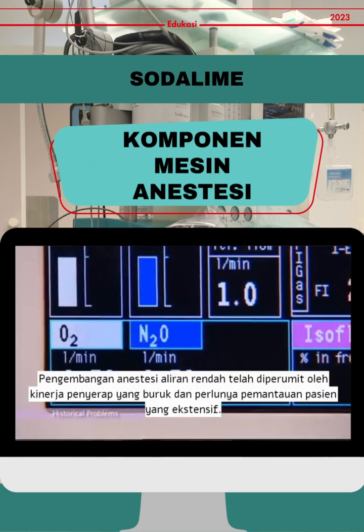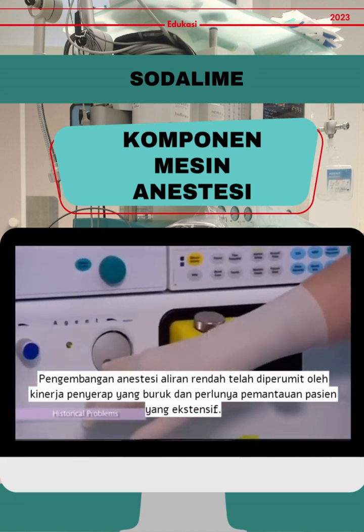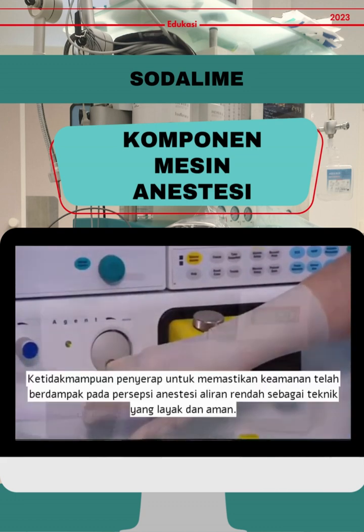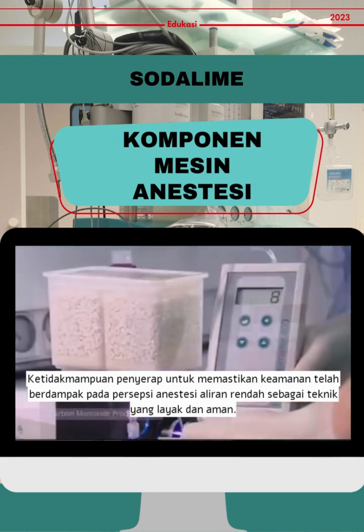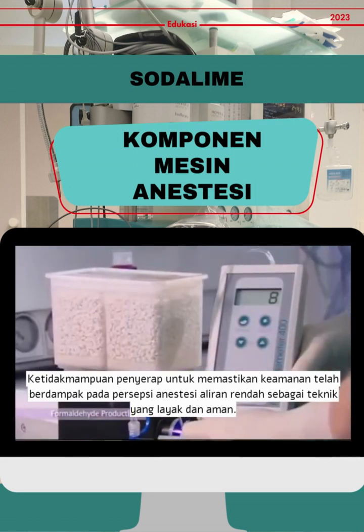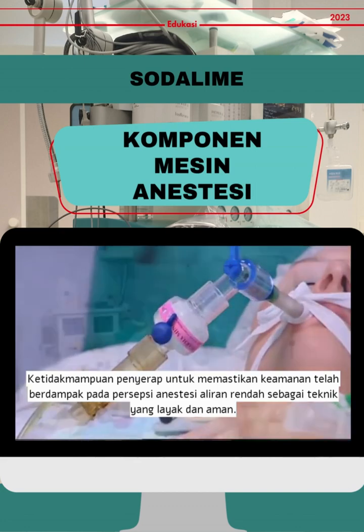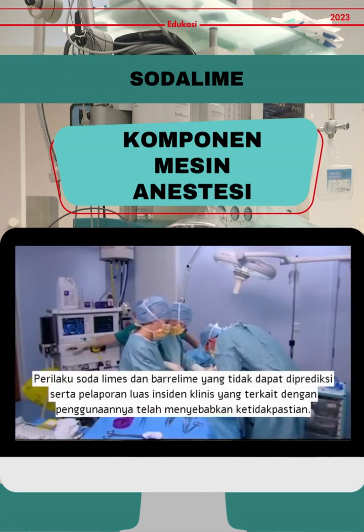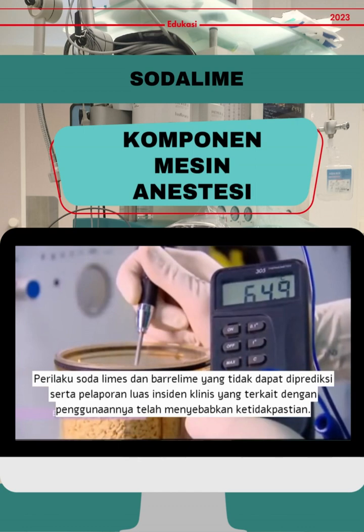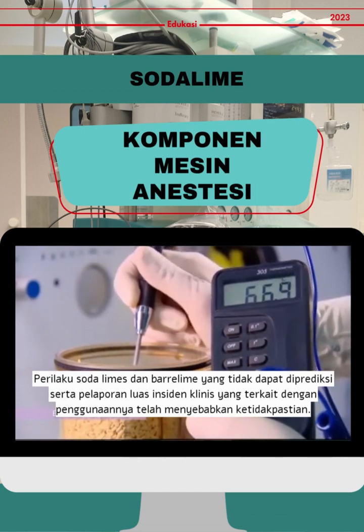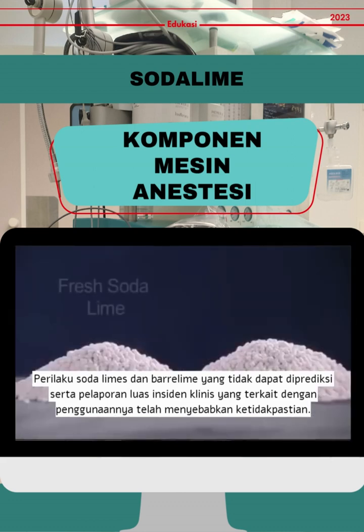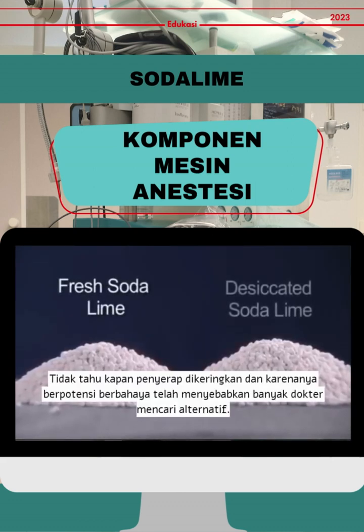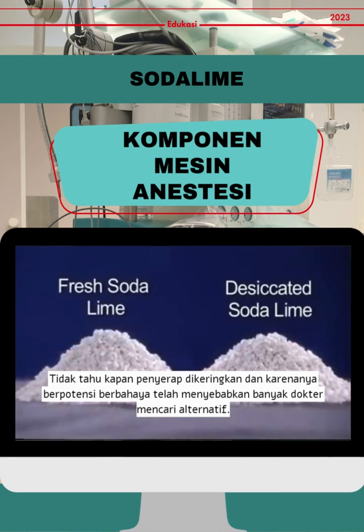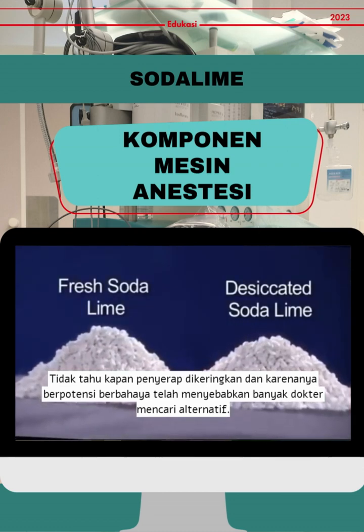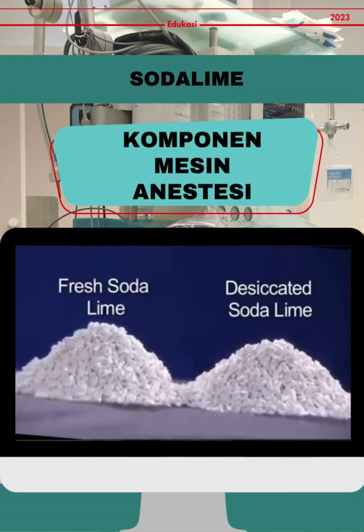Development of low-flow anesthesia has been complicated by poor absorbent performance and the necessity for extensive patient monitoring. The inability of absorbents to ensure safety has impacted on the perception of low-flow anesthesia as a viable and safe technique. The unpredictable behavior of sodalimes and Baralyme, as well as the widespread reporting of clinical incidents associated with their use, has led to uncertainty. Not knowing when absorbents are desiccated and hence potentially dangerous has led many physicians to look for alternatives.